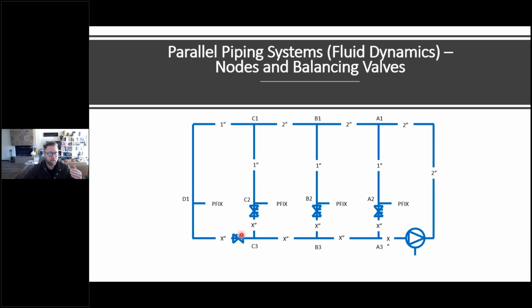But those balancing valves would create that artificial pressure drop across the valve that would push that water to the next path of least resistance all the way out through the rest of the system. And that's the purpose of the balancing valves that we have in this system.